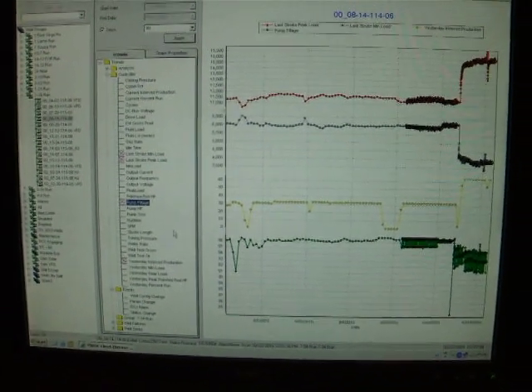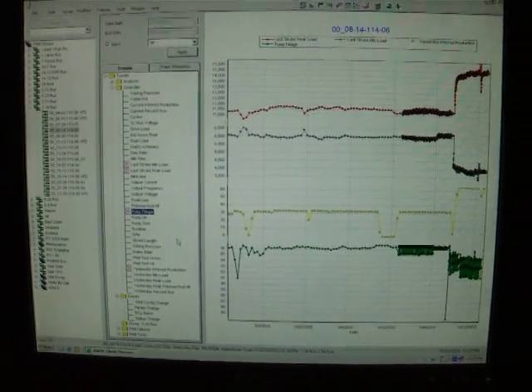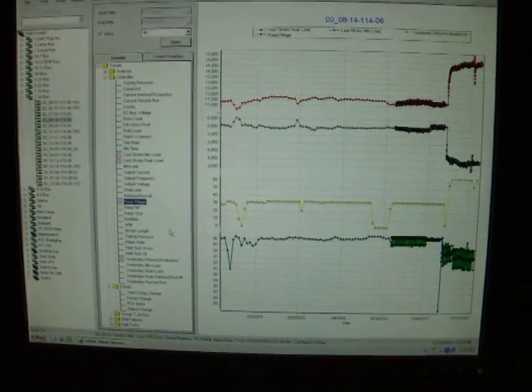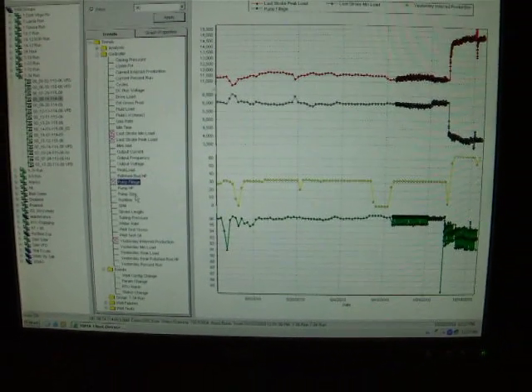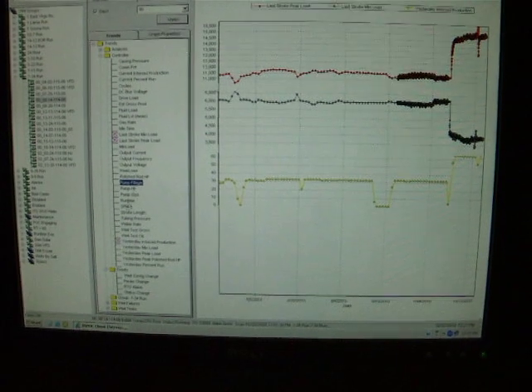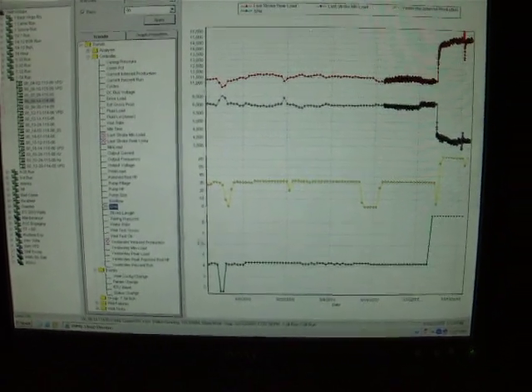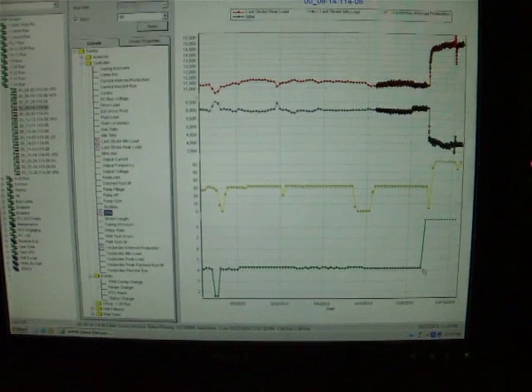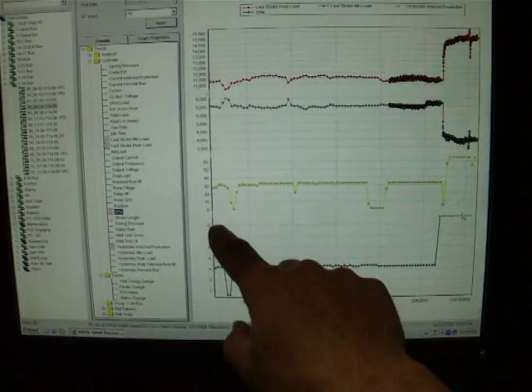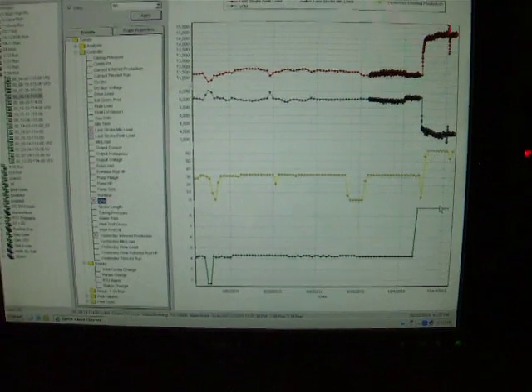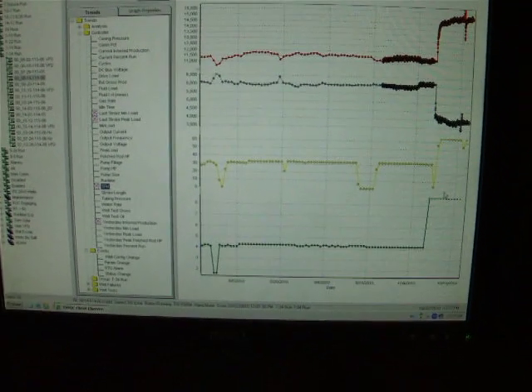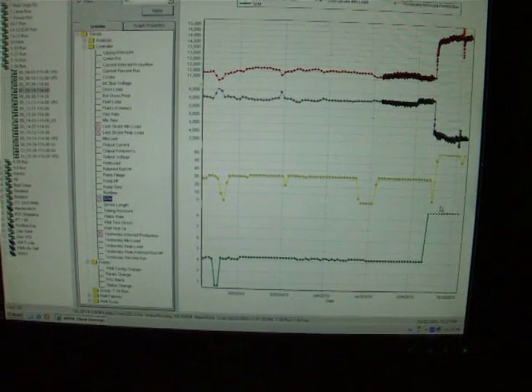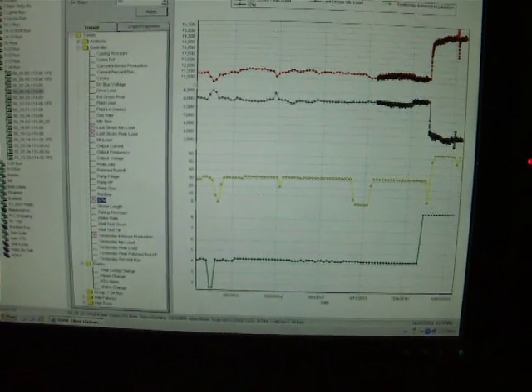This well does have a VFD on it and it likely sped itself up, which I can also check too. Looks like the speed went from 4 strokes a minute to 8 strokes a minute, 4 to 8. So it sped itself up on site. That's good info from a pump off controller taking care of itself.